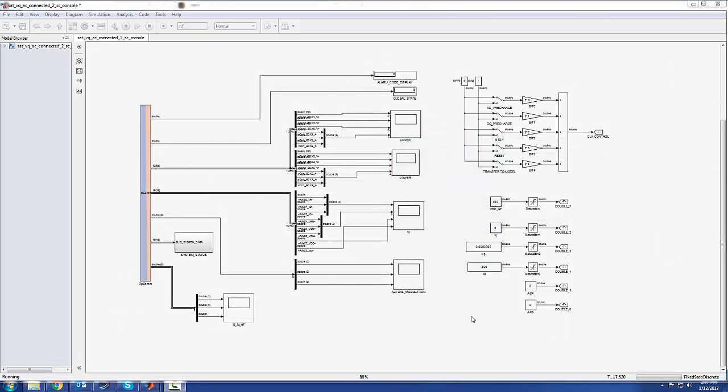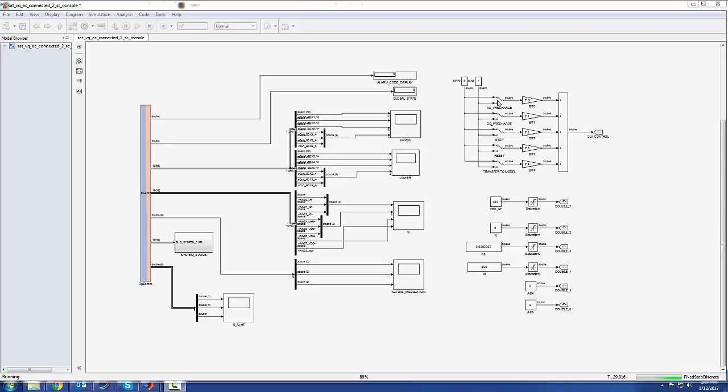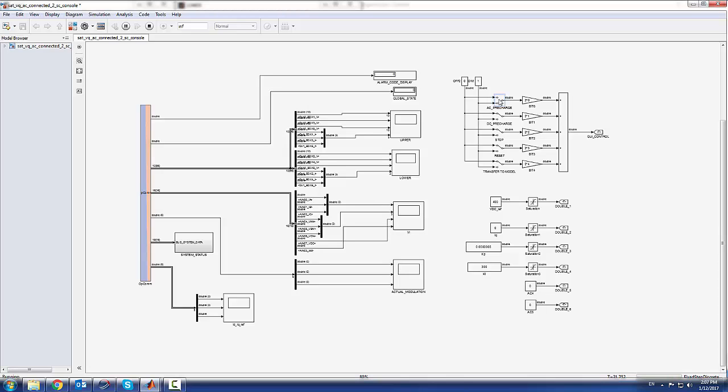Now my model was compiled and sent to the real-time simulator, the OP4510, to act as an MMC central controller. This is the console for this model where I access the different scopes on the variables of the MMC and the constants to my controller. I'll show you quickly how to start this converter. I have an AC pre-charge command switch that will ask for an AC pre-charge sequence. Once this is done, I'll close my AC and DC breaker to connect the converter to the grid. The converter will act as a STATCOM converter, just injecting vars to the network.